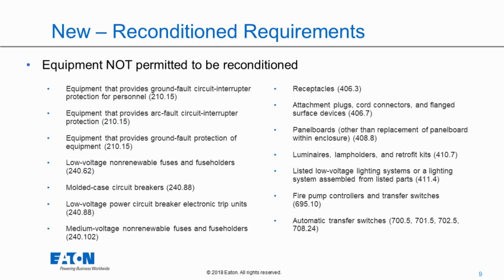Okay, next slide. When we look at what is not permitted to be reconditioned, we have equipment that provides ground-fault circuit-interrupter protection for personnel. We have equipment that provides AFCI protection or GFPE protection, molded case circuit breakers, and low voltage power breaker electronic trip units. So the low voltage and medium voltage power breakers can be reconditioned, but not their trip units. Also medium voltage nonrenewable fuses and fuseholders, and a lot of devices such as receptacles, attachment plugs, luminaires, and lampholders. We mentioned panelboards already, other than replacement of a panelboard within the enclosure. And of course, some other critical systems such as fire pump controllers and transfer switches are not allowed to be reconditioned.